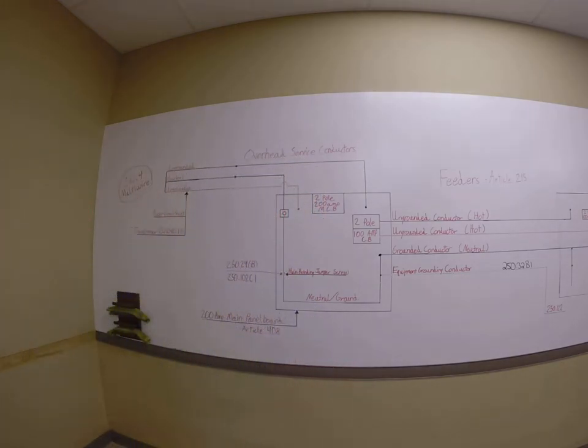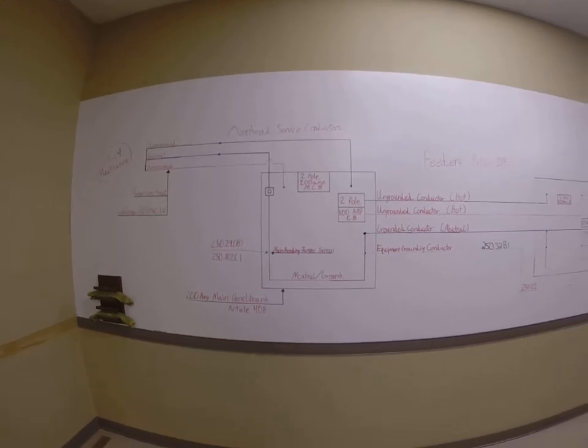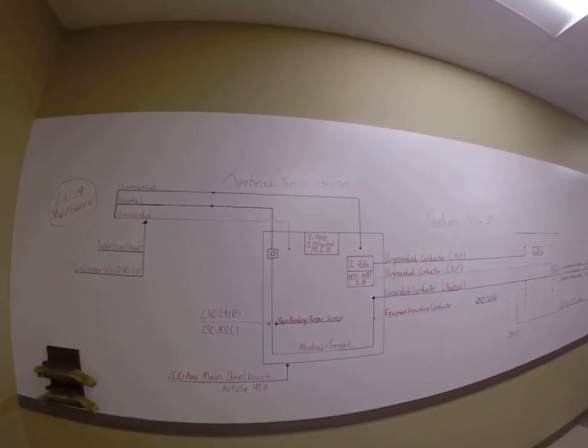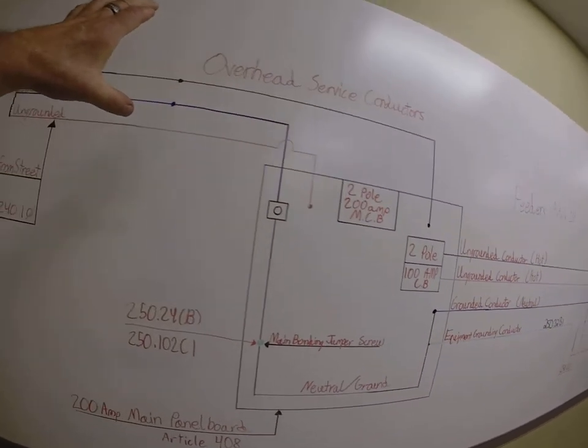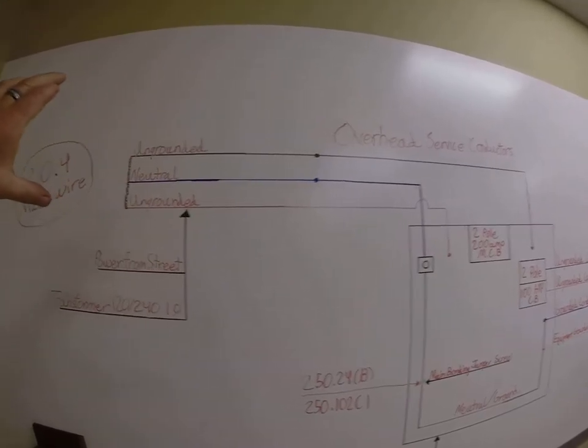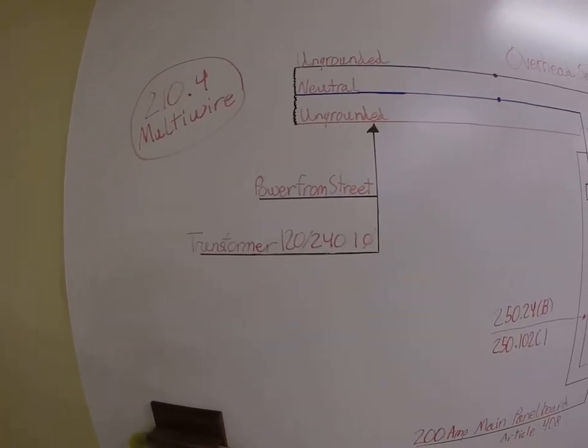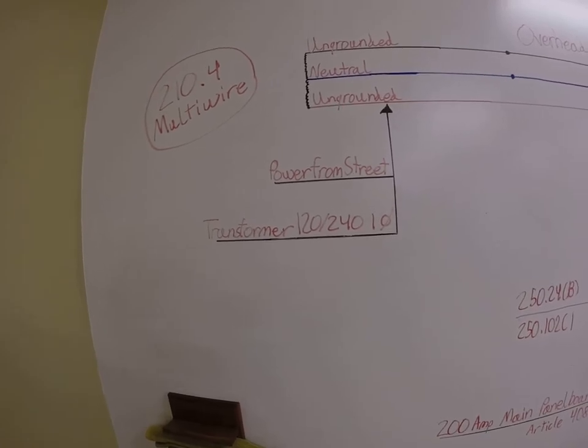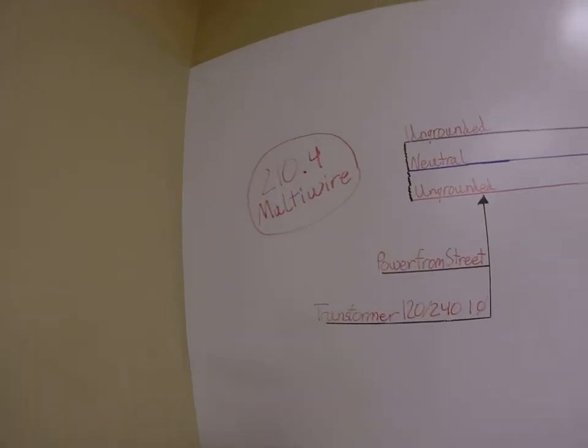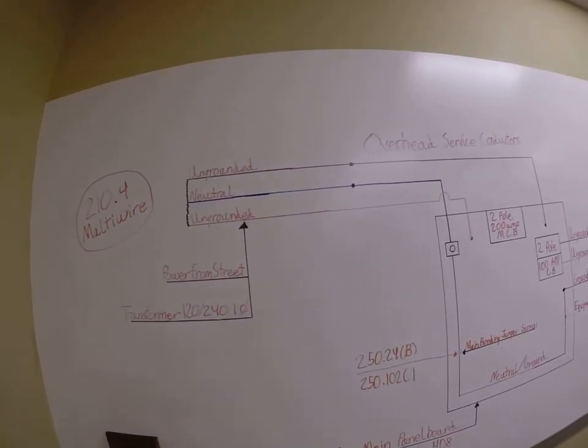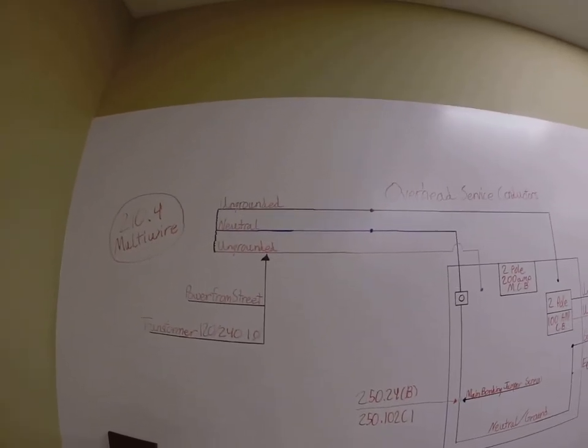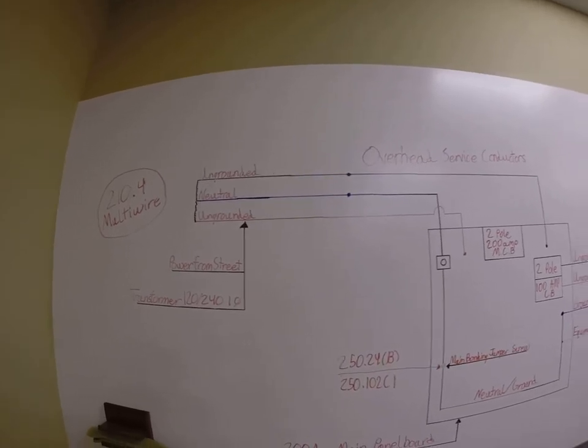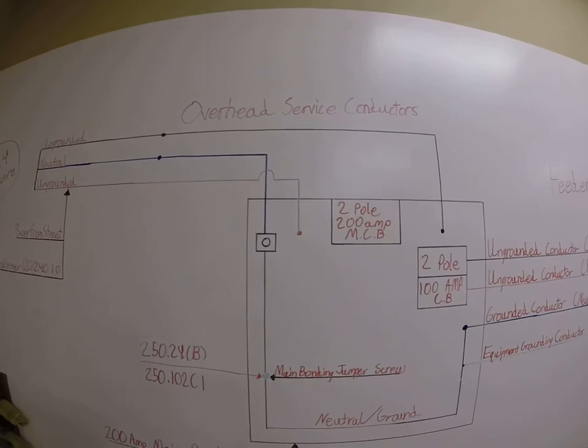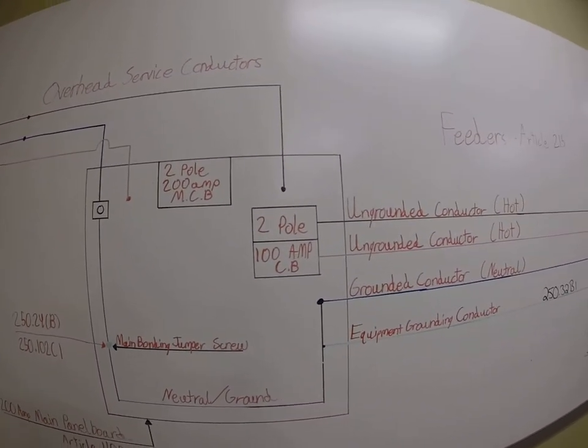Now, to go along with this, if you look at the illustration, let me get a better picture of it. I drew this 200 amp main panel with the assumption that your power is coming from the street, maybe an overhead tap right there. And then this is two ungrounded circuit conductors on the secondary side of the transformer, power from the street. Let's just say it's 120/240. Once again, it is a multi-wire circuit, 210.4, so we have to make sure we're sharing that neutral and that we simultaneously disconnect both ungrounded circuit conductors with a 2-pole circuit breaker, which we do with the main. We're also doing it with the sub-panel. It is a multi-wire circuit.